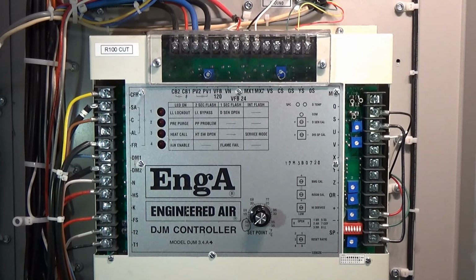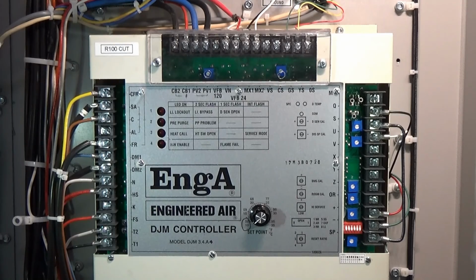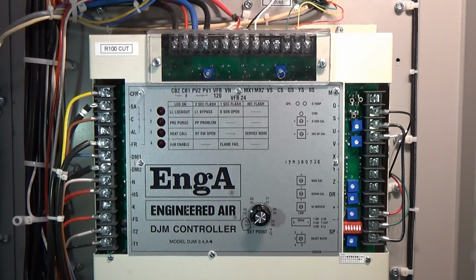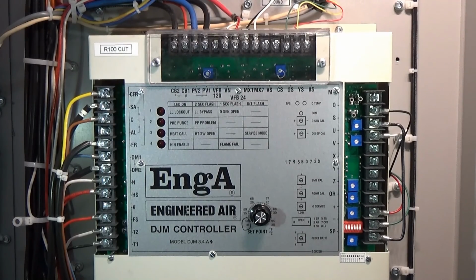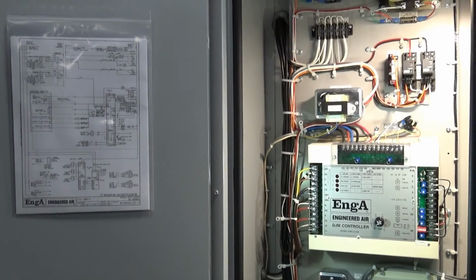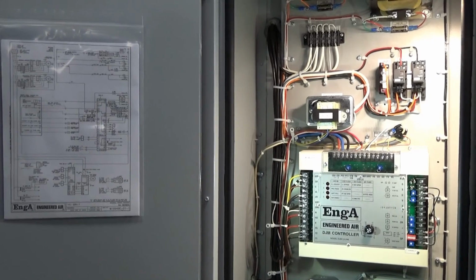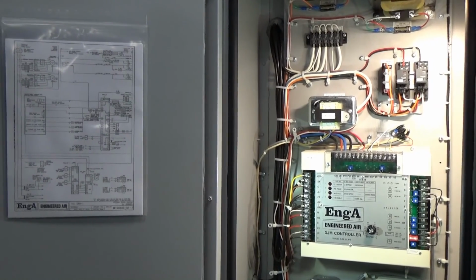The DJM 3.4 has several different setpoint options, from standalone face setpoint, remote panels standalone, to 0-10 reset, room reset, and even ambient reset. The setpoint calibration that we will cover is the standalone face setpoint dial on the DJM 3.4 board. To know what type of setpoint is controlling your unit, you should refer to the unit function page installed on the unit control cabinet door.